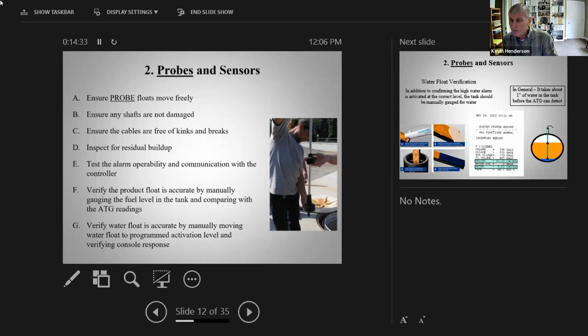Verifying the water float is accurate is also part of the deal. And it's not just the fuel float. So you look at your setup report and you see, okay, the high water warning and the high water limit are set at a certain inch level. Typically what you'll see is the high water alarm is set at 3 inches. That's very typical. I don't know why, but it just is. People will set it at 3 inches. So what you do, of course, is move the float to the 3-inch mark on the shaft and then verify that it does go into a high water alarm. And again, the whole idea is, are the floats measuring correctly?